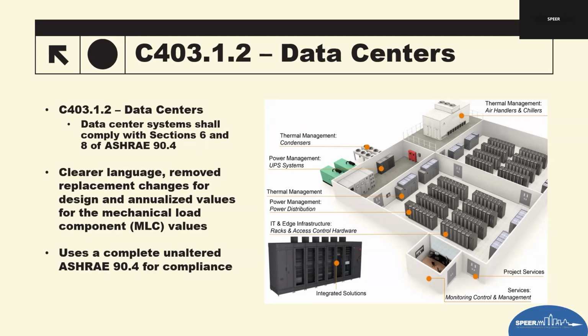So, plan review tip. When the project identifies itself as a data center, the plan reviewer must shift from IECC mechanical prescriptive requirements to an ASHRAE 90.4 checklist review. So the IECC's usual mechanical sections, including economizers, controls, and ventilation requirements, do not apply. I just put together, I think it's a 1.5 page data center checklist for plan reviewers that I'll also send out with the survey email.